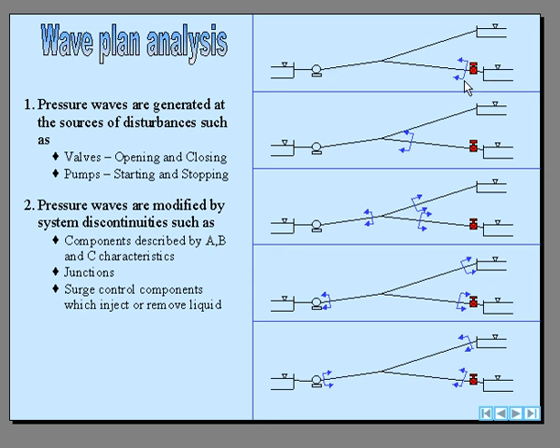The waves then travel at sonic speed, and at junctions, and at components such as pumps, they're reflected and transmitted. So this wave travels down this line at sonic speed. It now gets transmitted down the adjacent lines, reflected back into this line. These waves then go on. This wave travels to the pump, affects conditions at the pump, and gets reflected off of there.